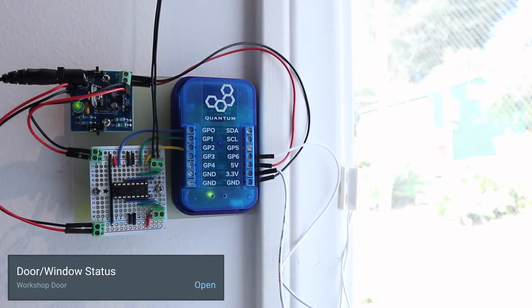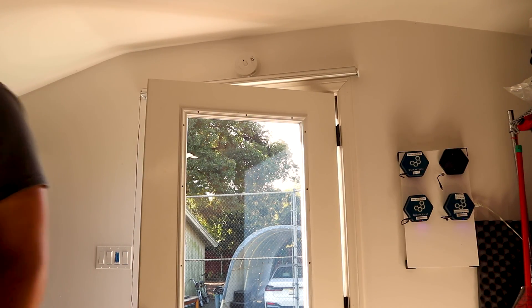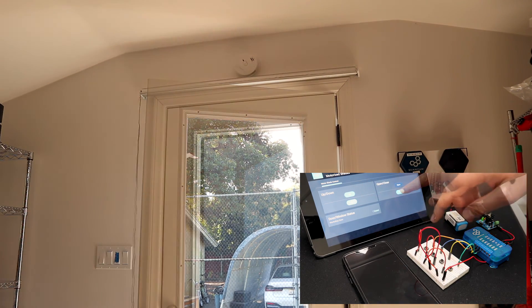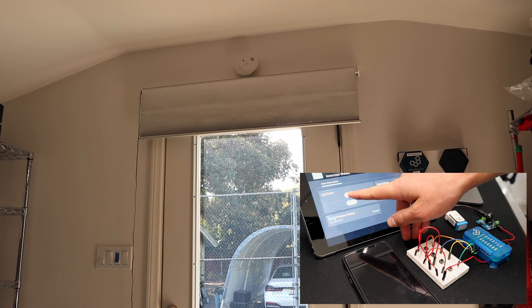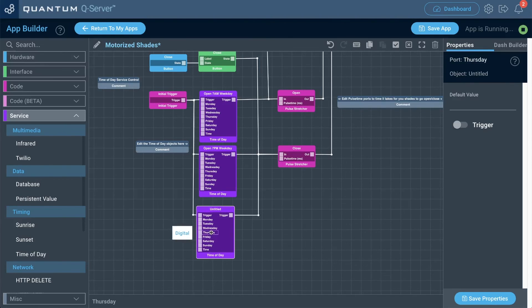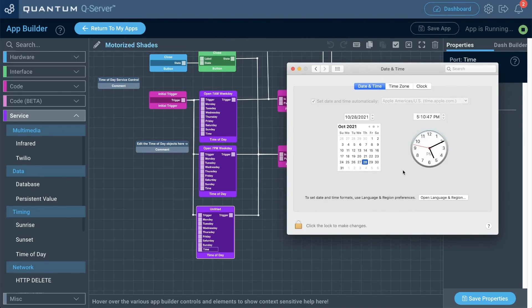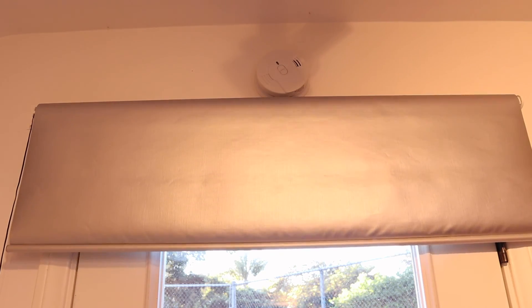Test that the pulse stretchers have enough time for the shades to fully open or close; add more time if needed. Test the door contact safety mechanism — open and close the door to verify the correct status appears on the dashboard, then confirm the shades won't move with the door open and will move when it's closed. Finally, test the time of day service by setting a time a couple minutes from now — at that time the shades should fully open or close. Once working, configuration and testing is complete.